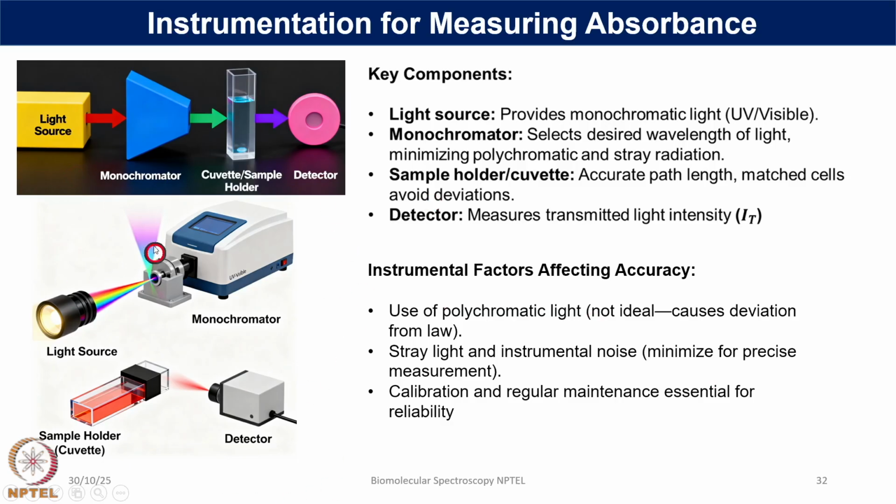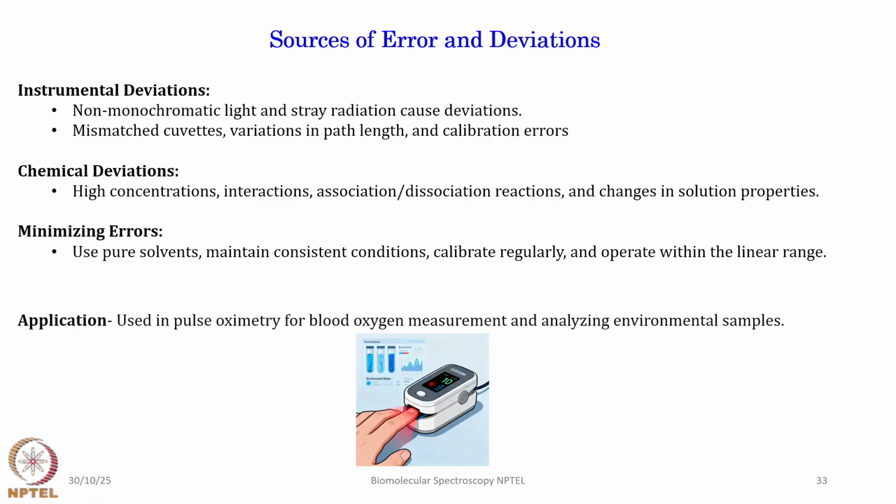A normal one comes at about 10 lakh rupees, but if you want to go for a very precise one, you have to spend a little more. So, calibration, maintenance, the lamp changing, the monochromator cleanliness, and most importantly your cuvette cleanliness. As a research scholar, you need to worry about the cuvette being clean; it should not have sticky walls where something else will be sticking. So, all those are important considerations, right.